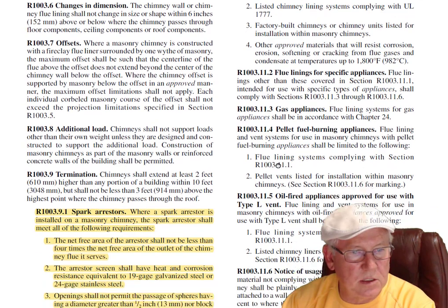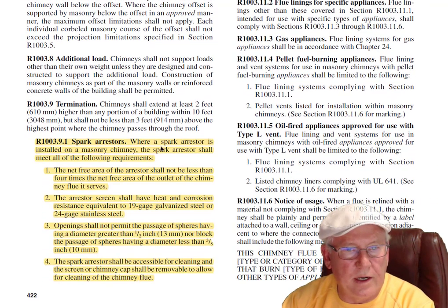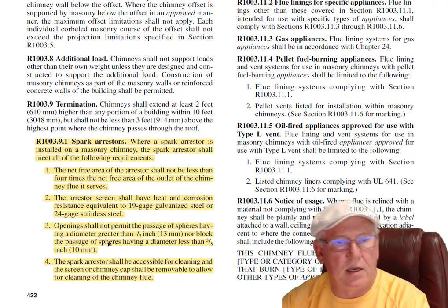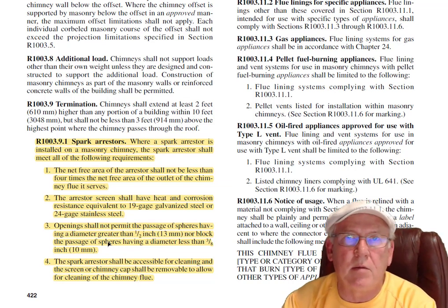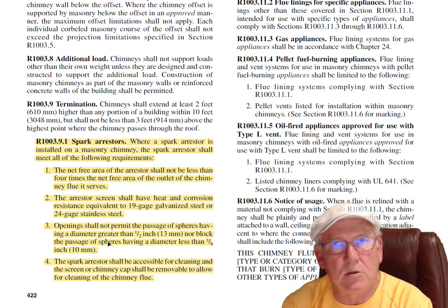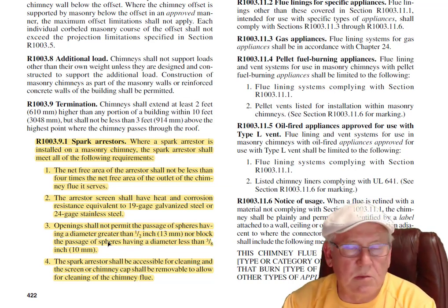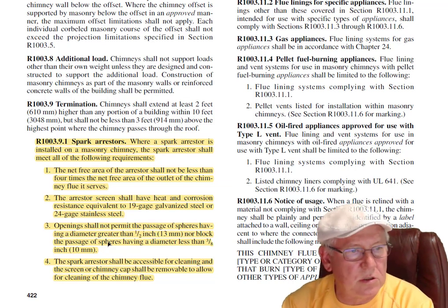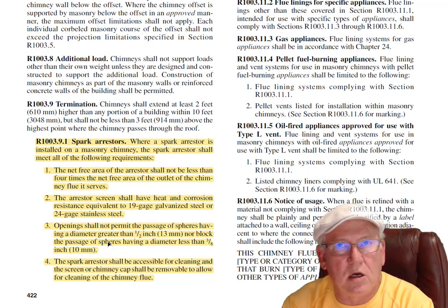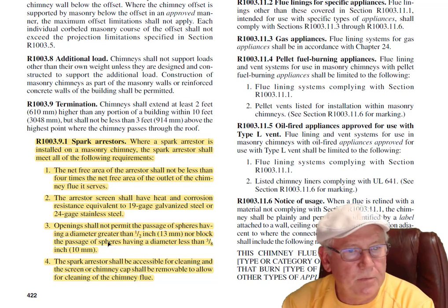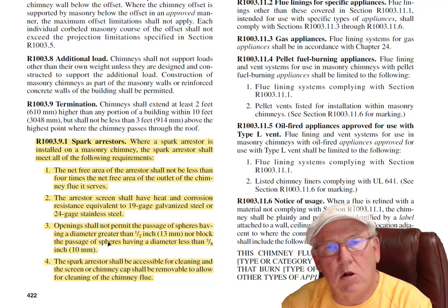The screen business, I just went ahead and highlighted this whole thing, but it talks about the screen being a minimum of 4 times the size of the flue. So these are some things for you to think about. Could cause you some issues as far as drafting issues. More clarity on the codes, building department in Charlotte.